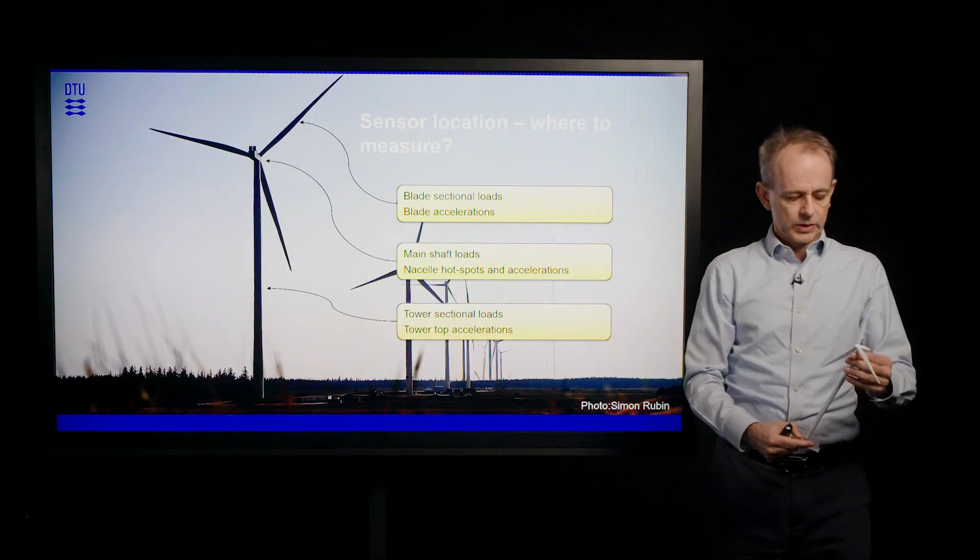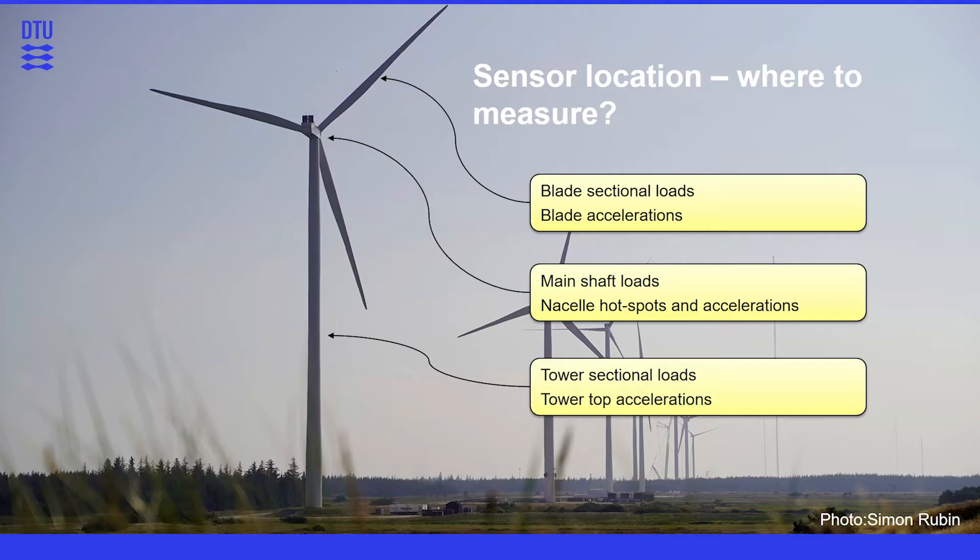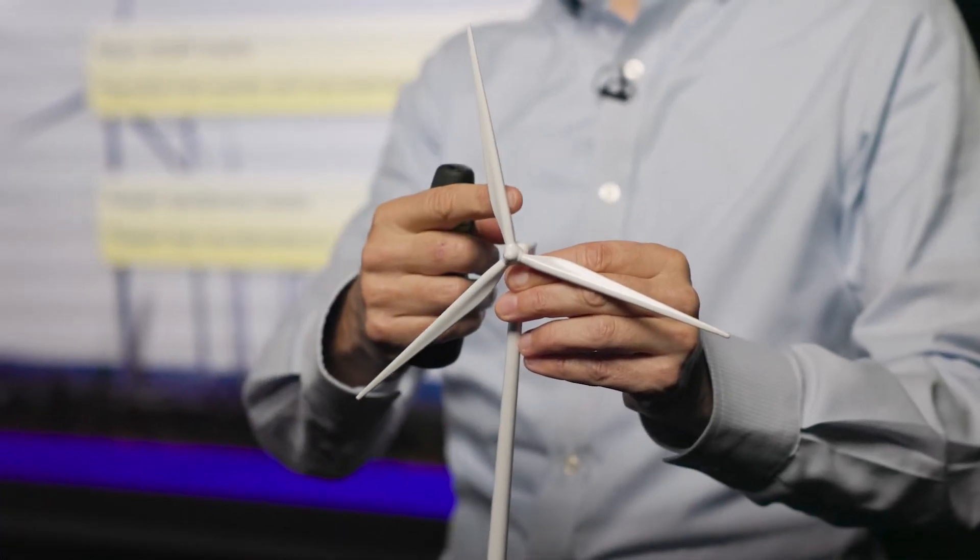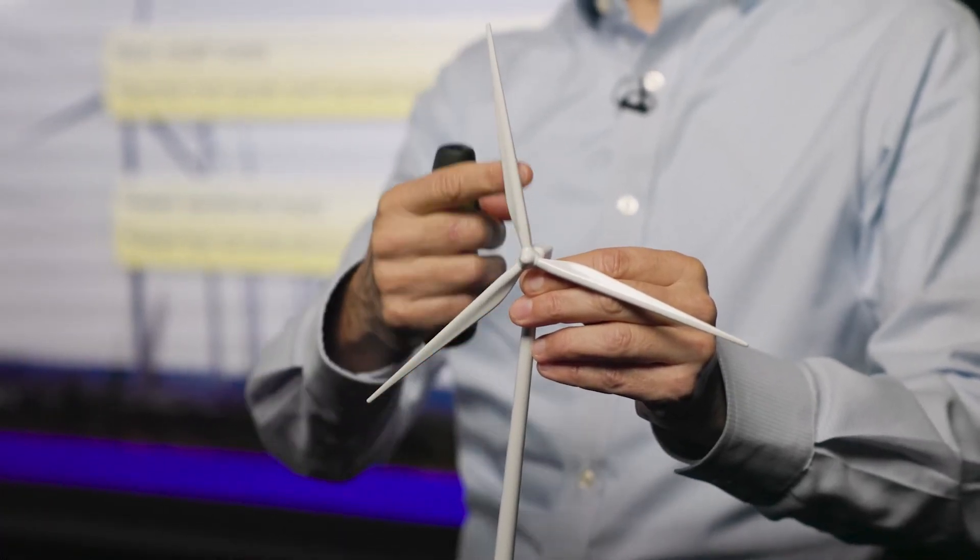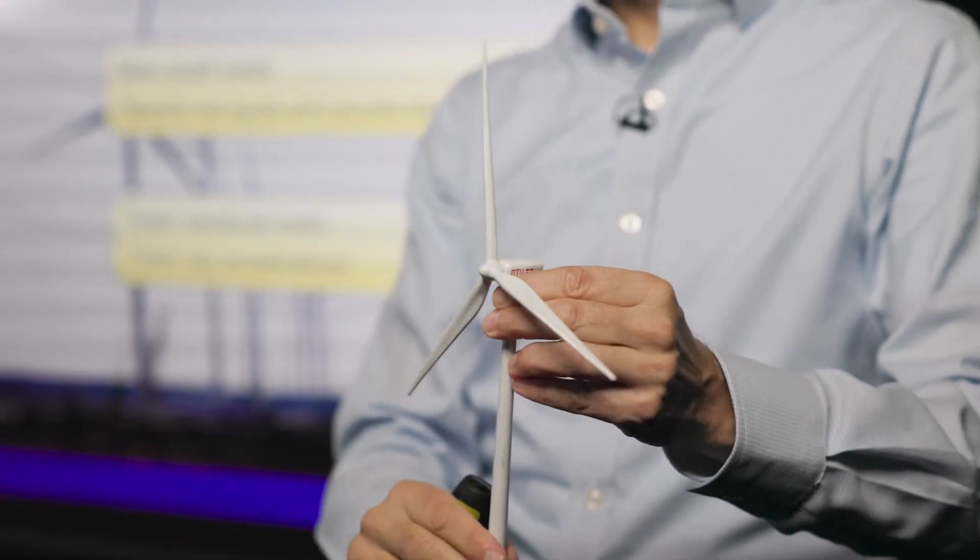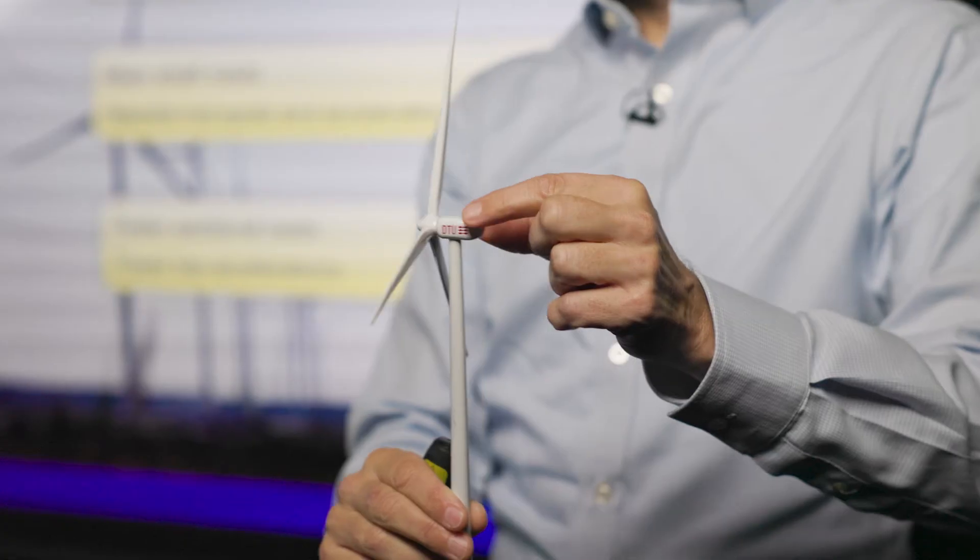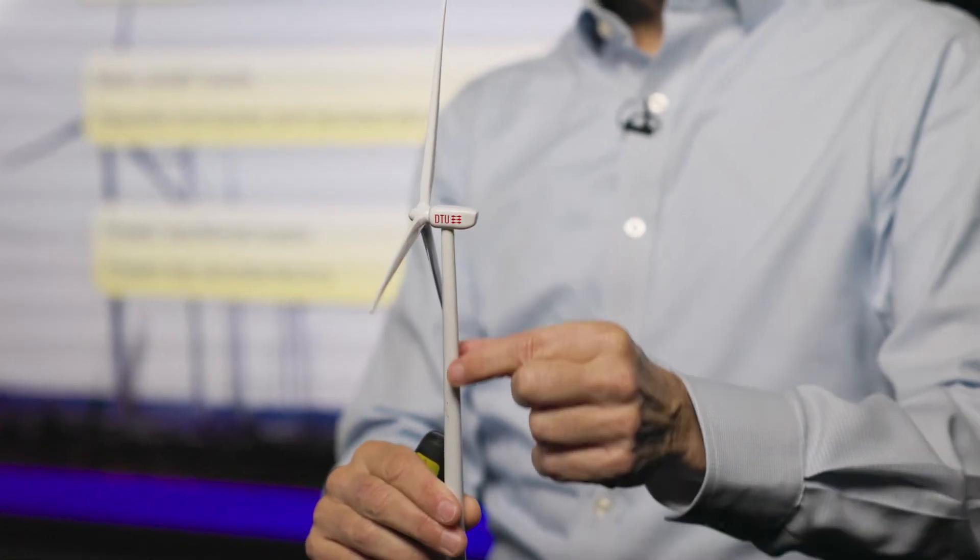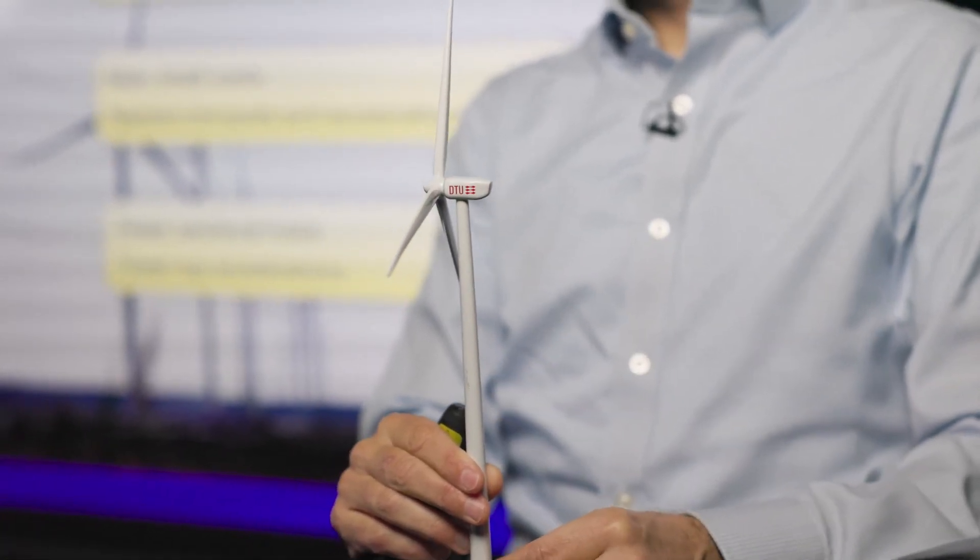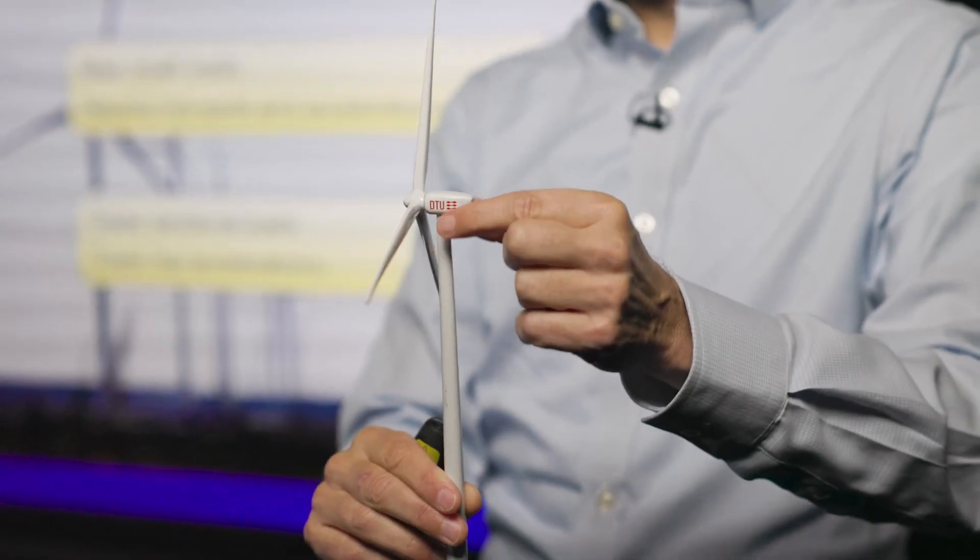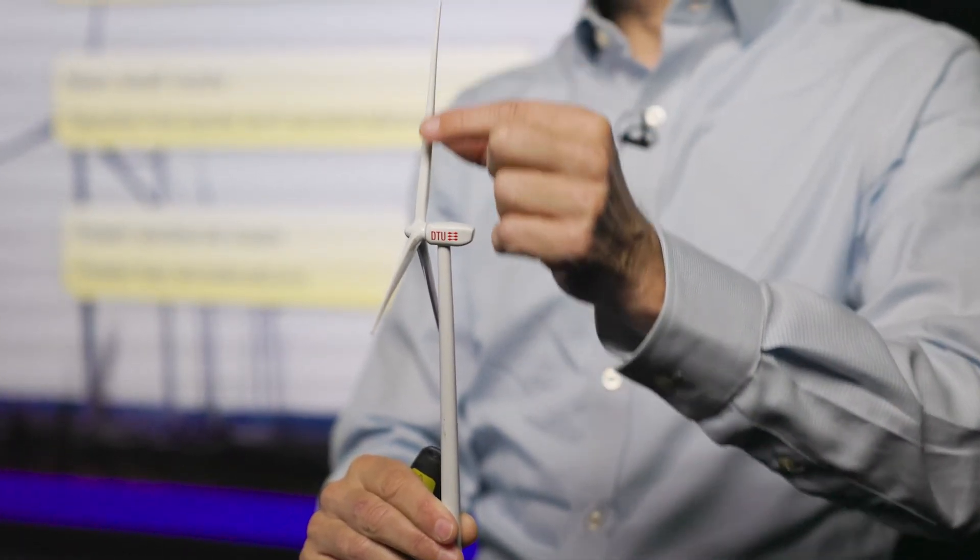When we talk about measurements, we measure at many different locations in the turbine. And typical measurements are done on the blades at different positions in the blades and different directions in the blade. It's measured in the nacelle of the turbine on the main shaft, and it's measured at various places along the tower. So we measure the sectional loads and accelerations in all of these places.